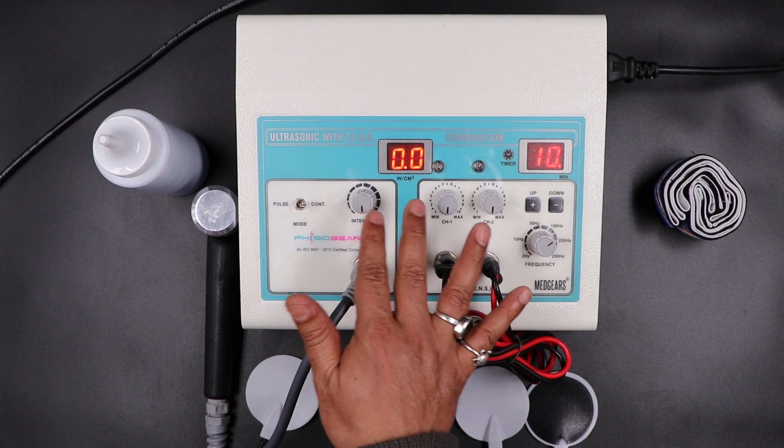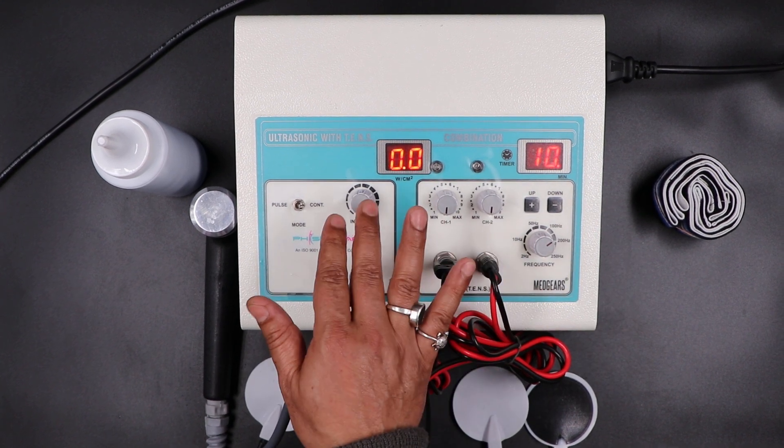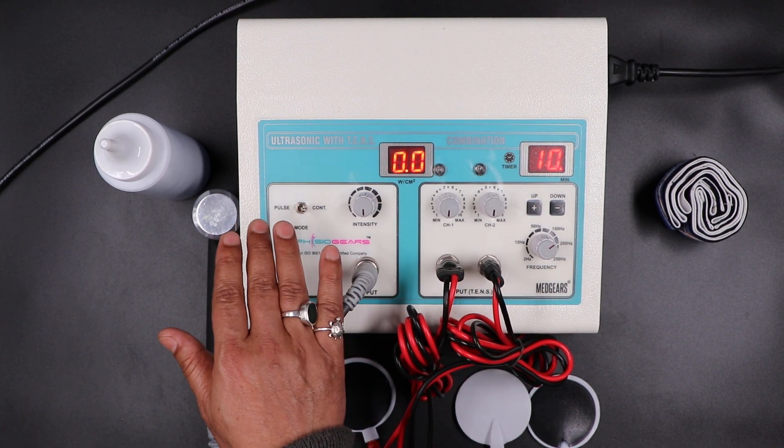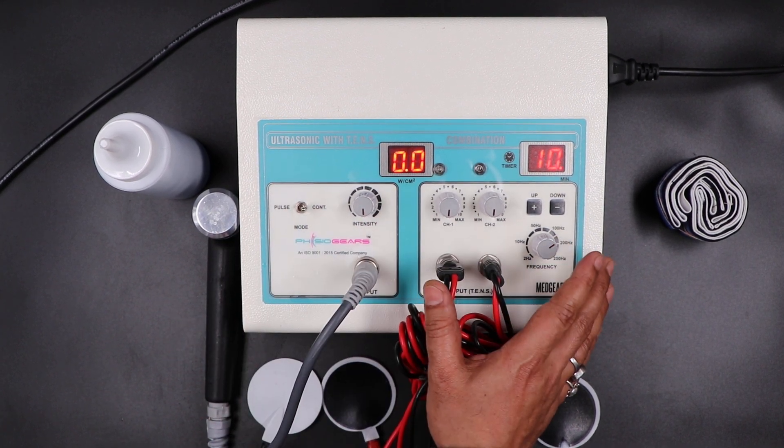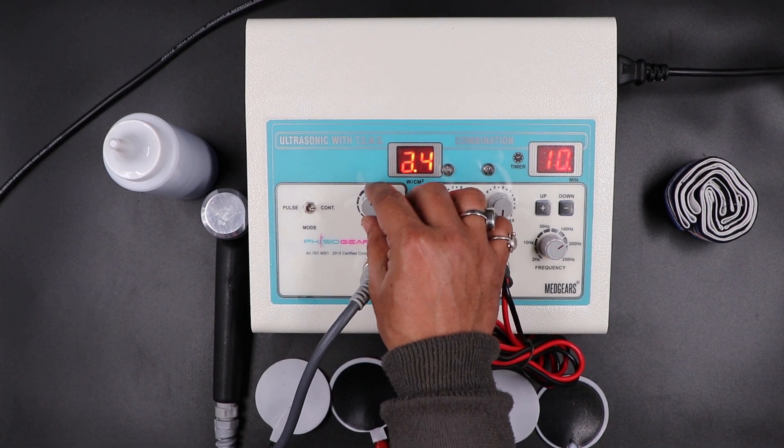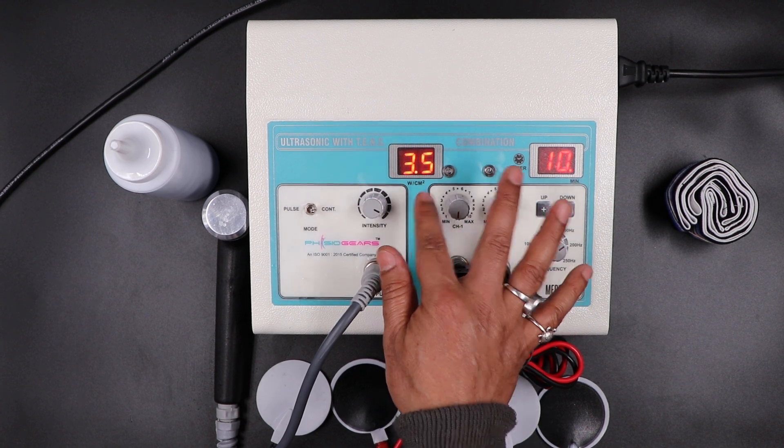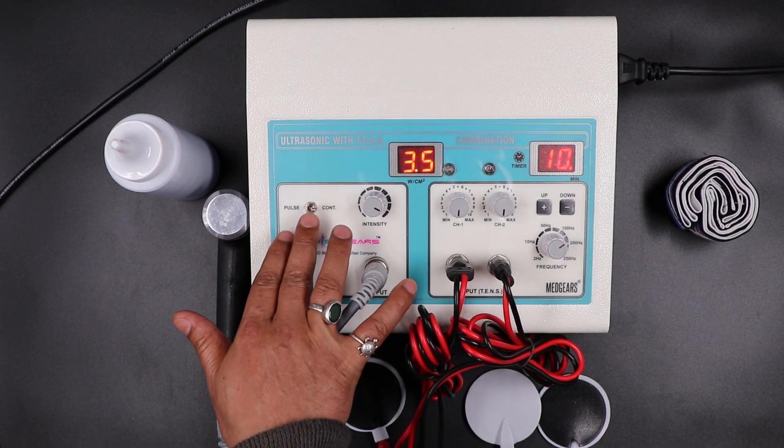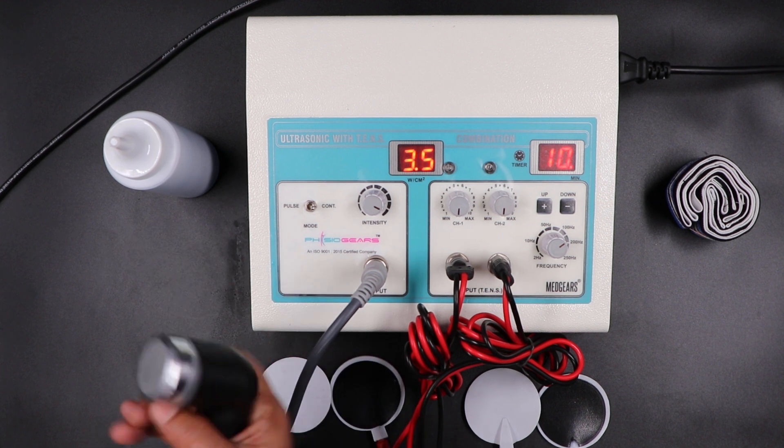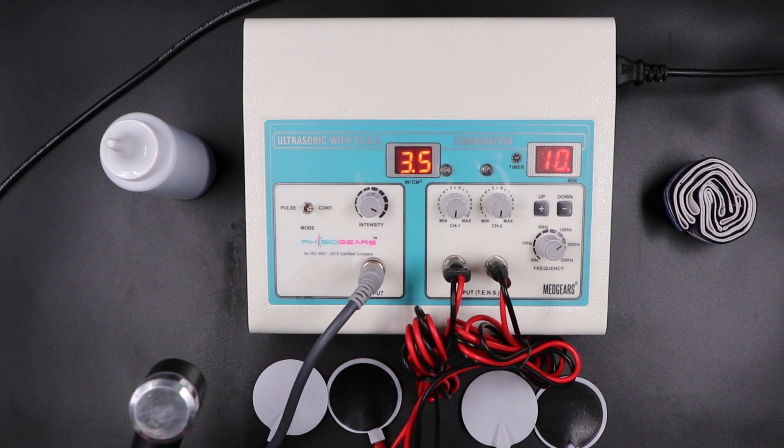You can see the intensity is zero zero. The left portion is for ultrasonic and the right portion is for TENS therapy. You can see the intensity is zero zero. Rotate the intensity at last, this is 3.5, and mode is continuous. We are checking the probe.